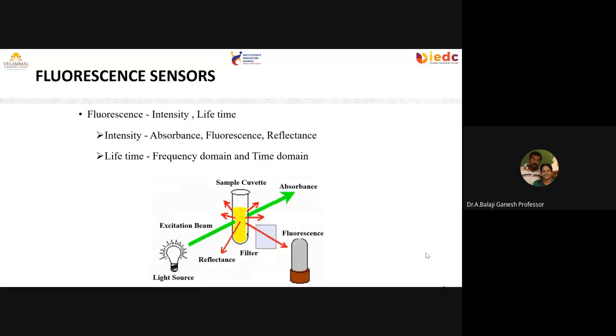So I was telling you about fluorescence and absorbance. If you want to measure the absorbance property of a certain sample, you can keep your detector and all those elements in a straight line, 180 degrees to your source light, whereas fluorescence is measured perpendicular to your light source. In that particular direction you can measure the fluorescence. These two concepts are, of course, subject to certain leaching. So people now are using lifetime measurement by incorporating frequency domain and time domain measurements.